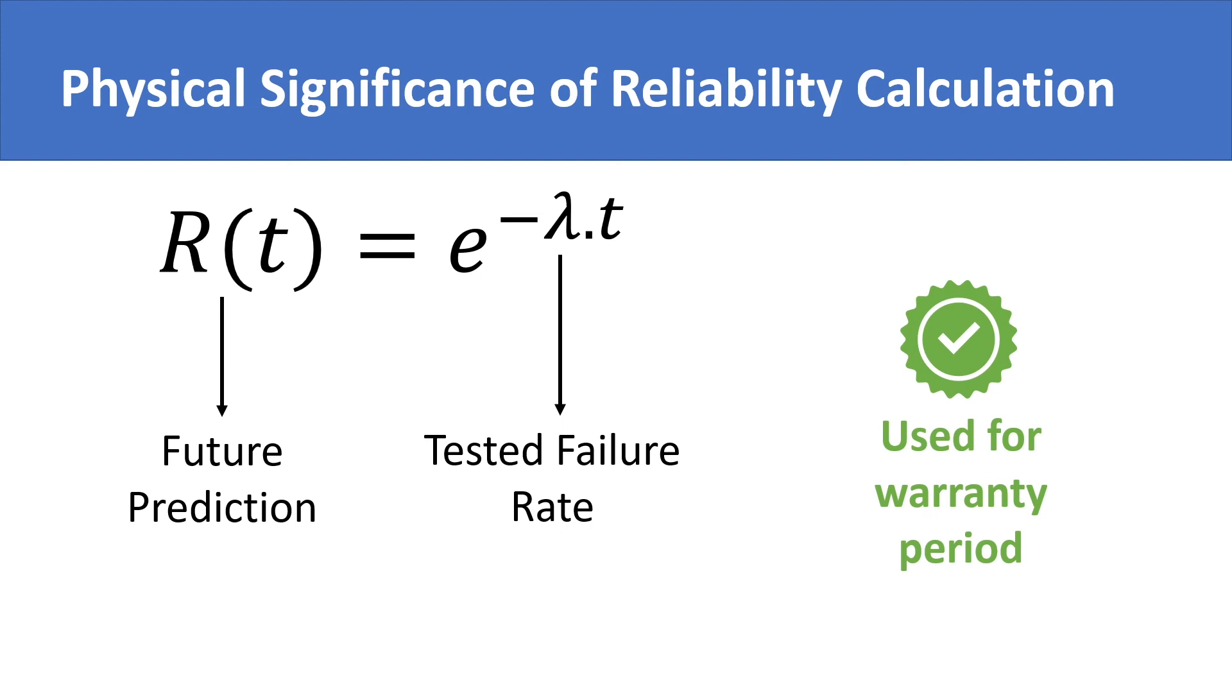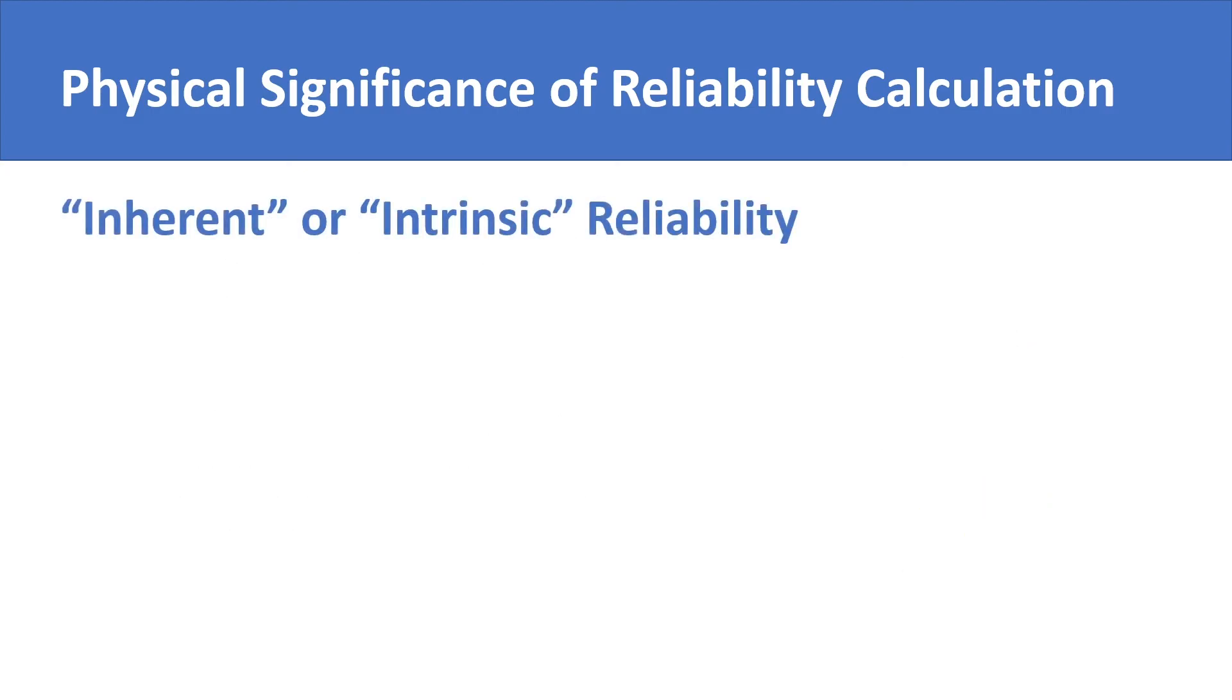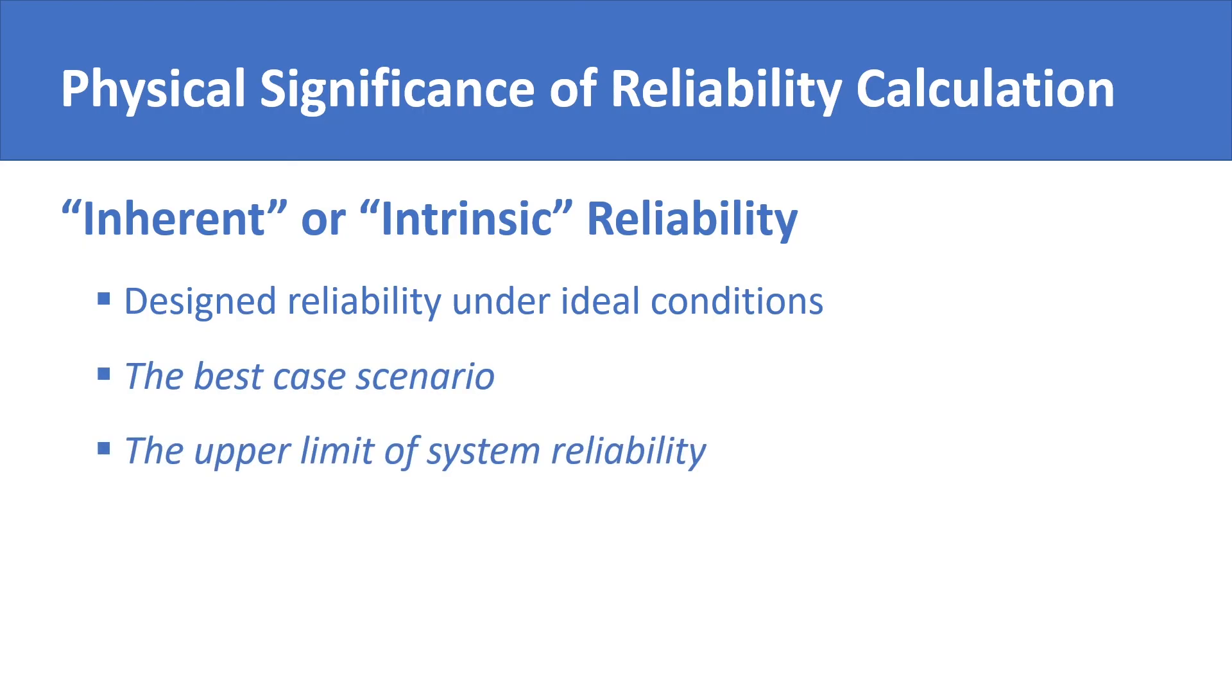An important concept to highlight here is that of inherent or intrinsic reliability. It is the design reliability of the system under ideal conditions. It is the best case scenario and the upper limit of reliability of a machine. No amount of maintenance can increase system reliability beyond its inherent reliability.